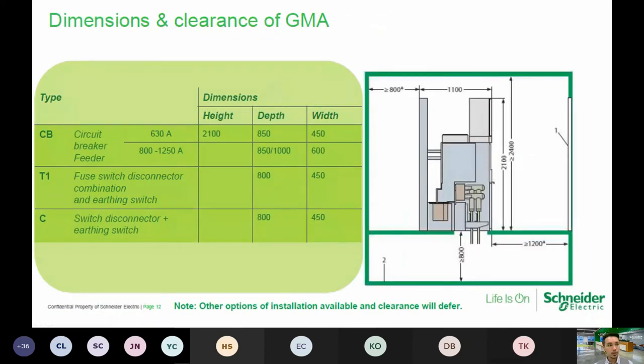So this slide in here talks about the dimensioning and clearance of the GMA. All right, so it talks about the footprint and also, if it's on a raised floor, what is the recommended height of the raised floor, if it's at the rear access. Of course, this switchgear can be moved against the wall. All right, even the side of the switchgear can be pushed to the side of the wall as well, but of course the consequence is that once it's been pushed to the end of the side of the wall, then extension is not possible at a later stage.